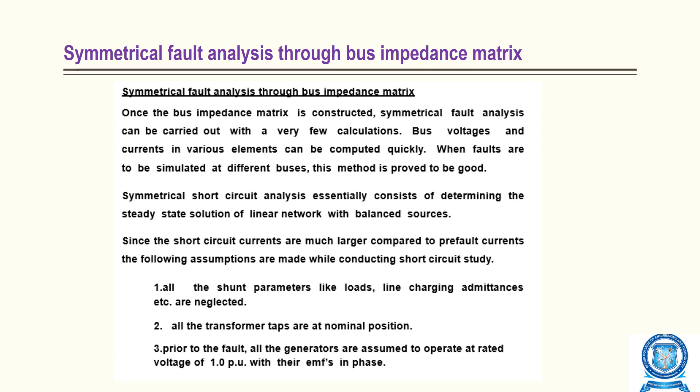Symmetrical short circuit analysis essentially consists of determining the steady-state solution of a linear network with balanced sources. Since short circuit currents are much larger compared to pre-fault currents, the following assumptions are made: all shunt parameters like load line charging admittance are neglected, and all transformer taps are at nominal position.